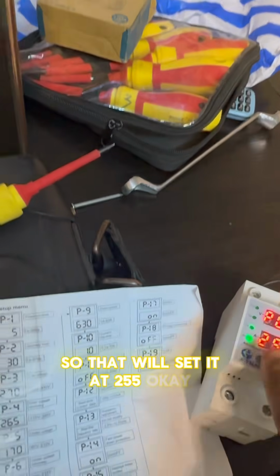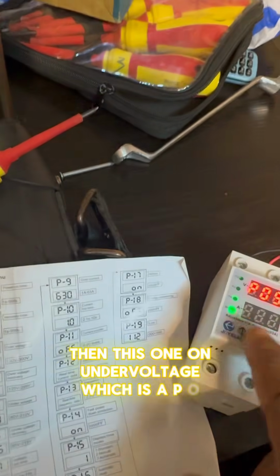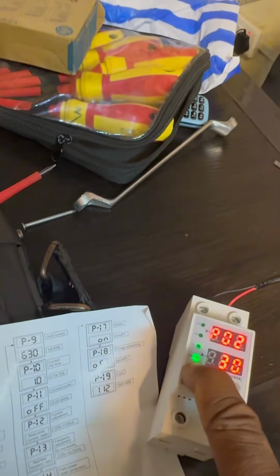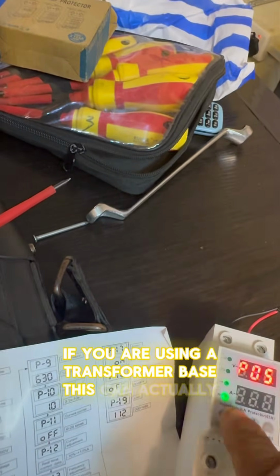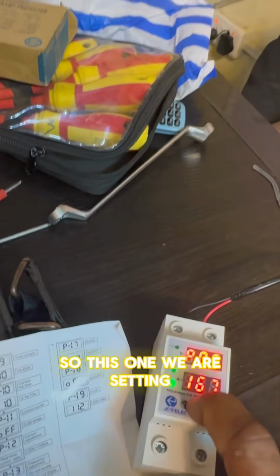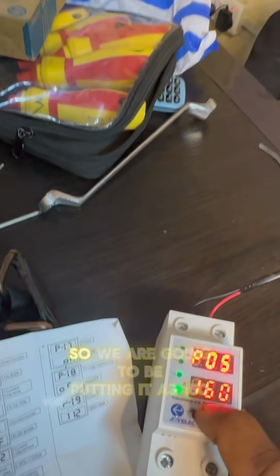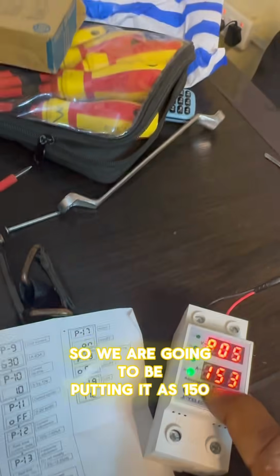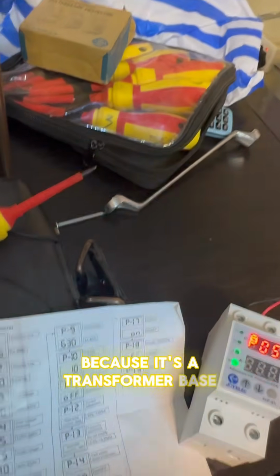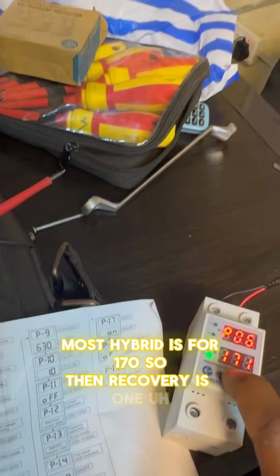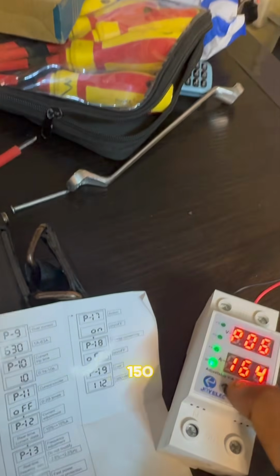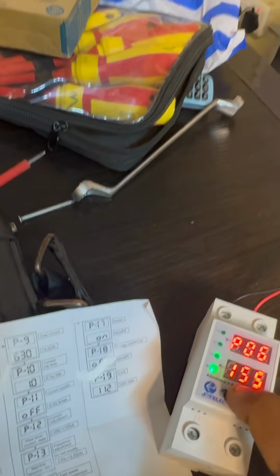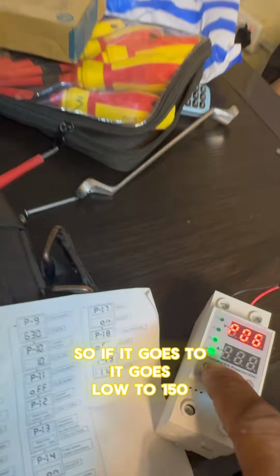Okay, 255. Then this one, under voltage, which is PO5, under voltage 170. If you are using a transformer base, this can actually go lower. So this one we are setting for a transformer base system, so we're going to be putting it as 150. But if you're using a hybrid system, most hybrid is 170. So then the recovery is 150. So if it goes low to 150, you need to go high to 155 before it can reconnect.